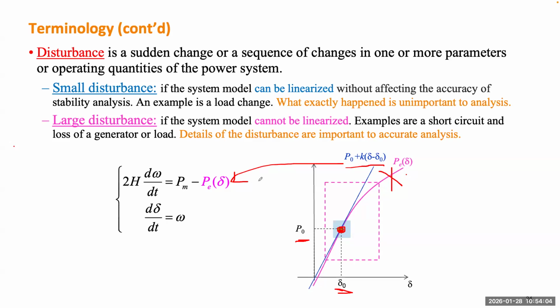But if a disturbance can push the system outside of this region to this bigger rectangular area, you see the two curves are very different, right? The difference will affect the result, so you have to go back to the nonlinear curve. So staying inside this blue region, the disturbance can be considered small, but outside of this region, where the linear approximation is different from the original nonlinear curve, you have to treat the disturbance as a large disturbance. There is no standard saying which contingency list will always be small and which will always be large. The question will be asked to the engineers and operators: what accuracy do they want to achieve?